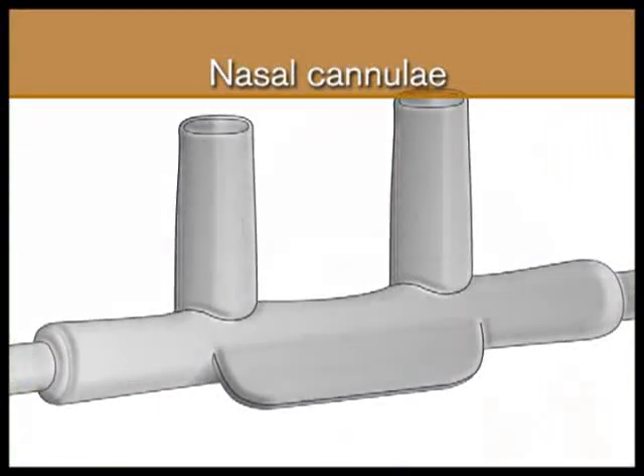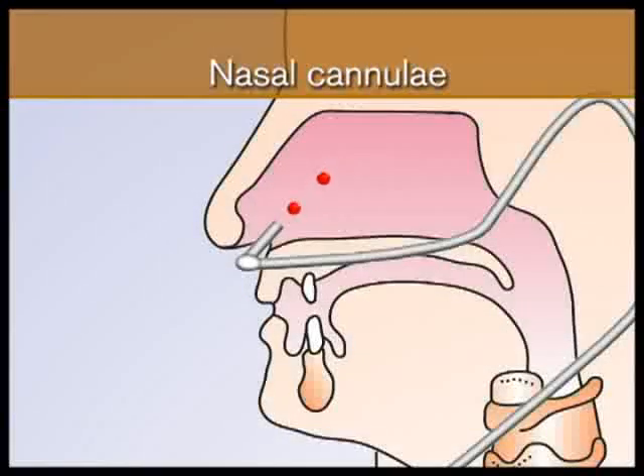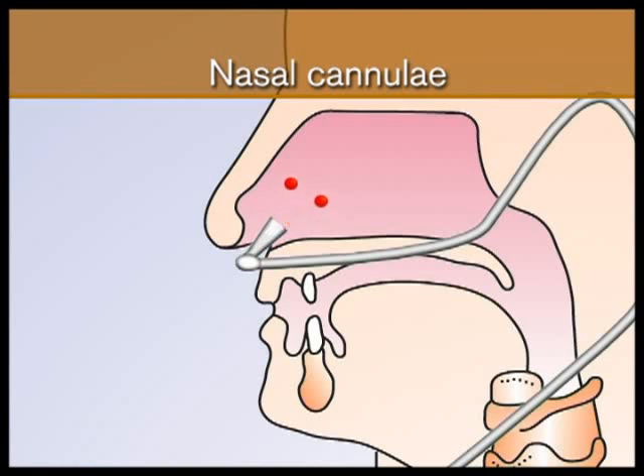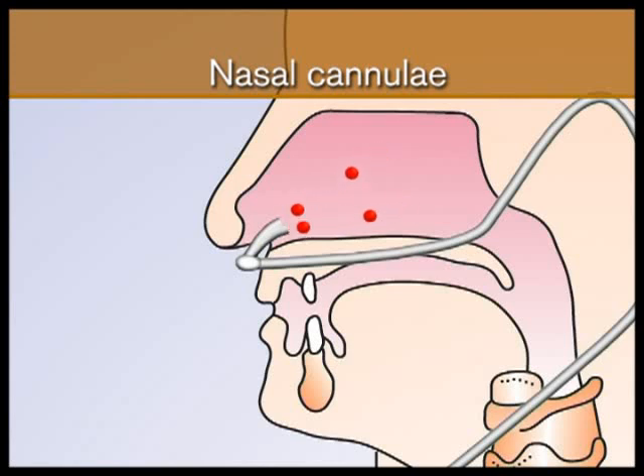Straight prongs are the original design and are still the most frequently used in hospitals. Curved prongs are designed to direct the flow of oxygen posteriorly rather than upward towards the frontal sinuses. Flared prongs have an increased diameter towards the tip, which has the effect of slowing down the gas as it enters the nose, making it more comfortable for the patient. Curved and flared prongs combine the best features of the two options, releasing oxygen more slowly and away from the frontal sinuses.